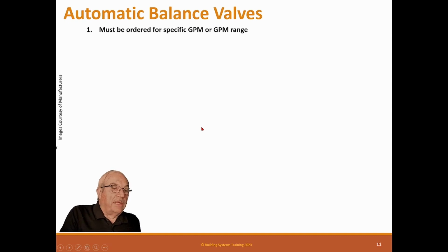All right, now we're going to talk about automatic balance valves. So they have automatic balance valves that were built to self-balance the system. You put these on downstream of a coil, and they're actually spring-actuated valves. They have a little cup in there with a spring behind it, and as the flow pushes it in, it has slots that get bigger or smaller and let more or less flow in. So they do work. There's a couple of things you have to consider about automated valves. One is they do increase system pressure because you're always pushing against that spring, and that's some pressure. Might not be significant, but it is pressure. It does cost money to run forever.